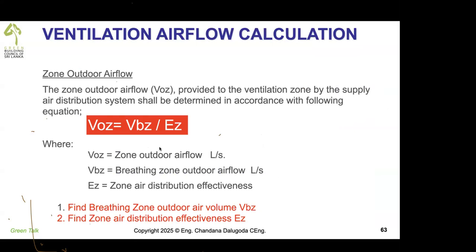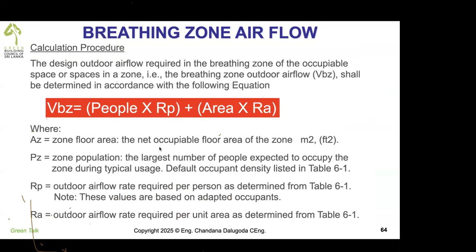So ASHRAE 62.1 gives you how to calculate your outdoor air volume, outdoor air flow. You'll have to calculate breathing zone volume and divide by zone effectiveness. Breathing zone calculation is very simple. You need to know how many people and rate per person, a figure. We can get it from a table. And you should know the area of the space multiplied by rate per area. These figures are given by table in the 62.1.